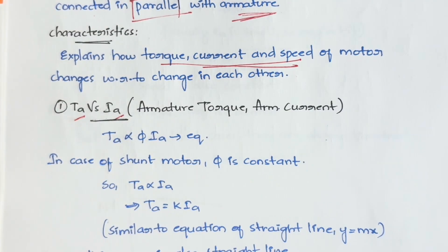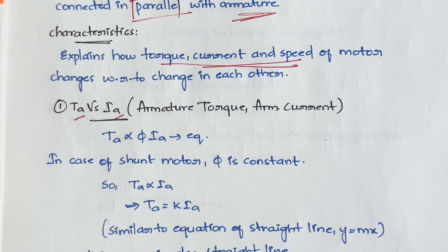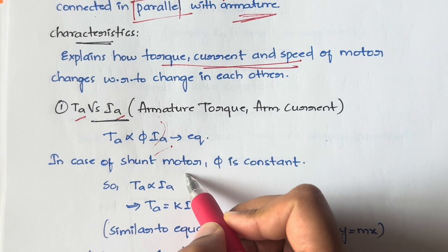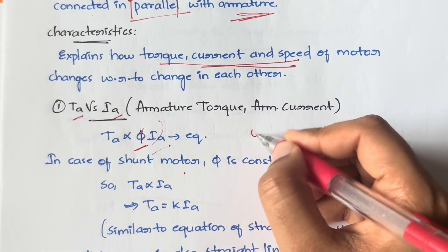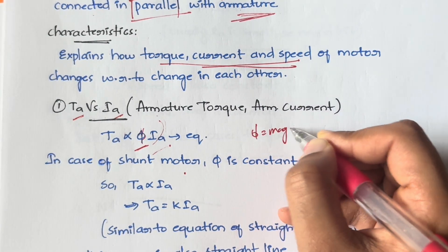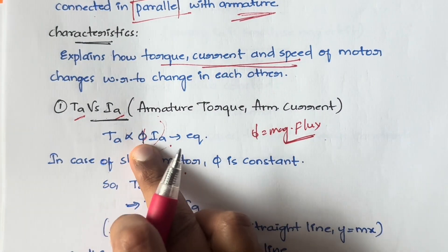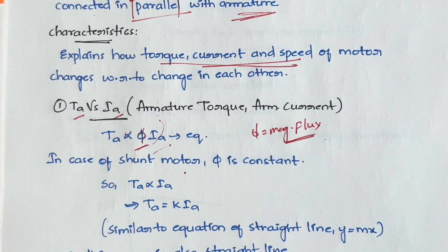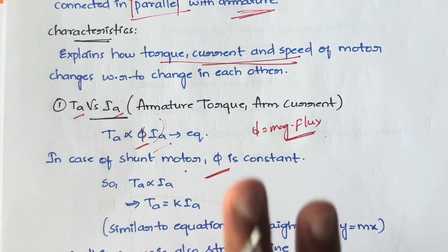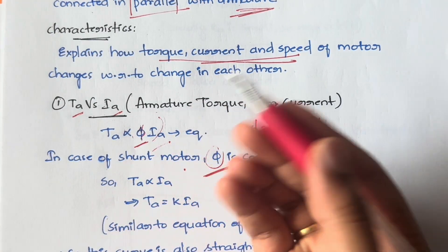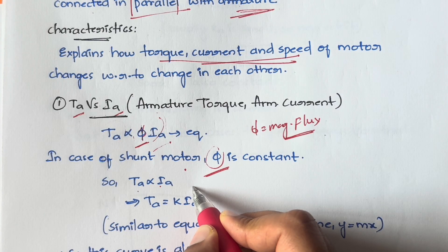Armature torque is directly proportional to armature current. In the case of a shunt motor, armature torque is directly proportional to φ times Ia, where φ is the magnetic flux. So armature torque is directly proportional to both flux and current. In the case of a shunt motor, magnetic flux is always constant, so you can remove it and say Ta is directly proportional to Ia.